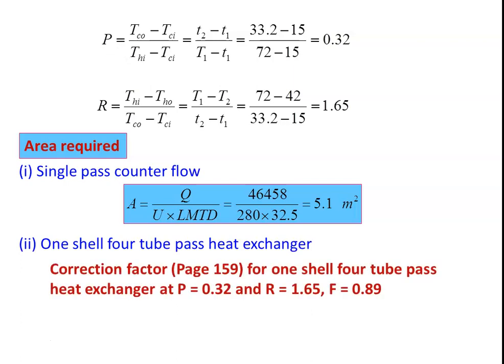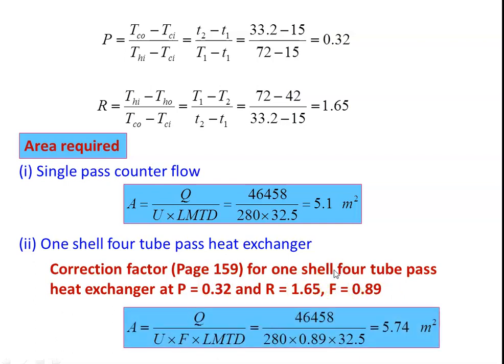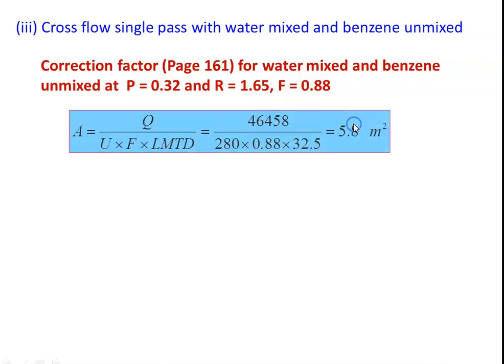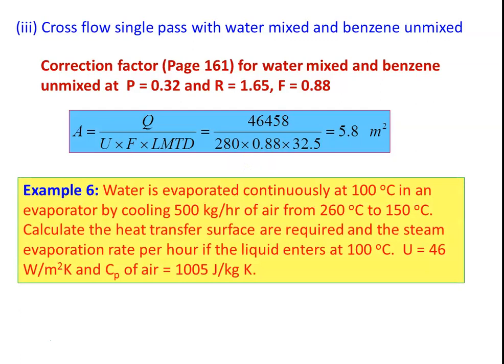For the one shell four tube pass configuration: from page 159 with P = 0.32 and R = 1.65, correction factor F = 0.89. Area = Q/(U × F × LMTD) = 46,458/(280 × 0.89 × 32.5) = 5.74 m². For the cross flow heat exchanger with water mixed and benzene unmixed: from page 161, F = 0.88. Area = Q/(U × F × LMTD) = 5.8 m². The three cases thus require 5.1, 5.74, and 5.8 m² respectively.